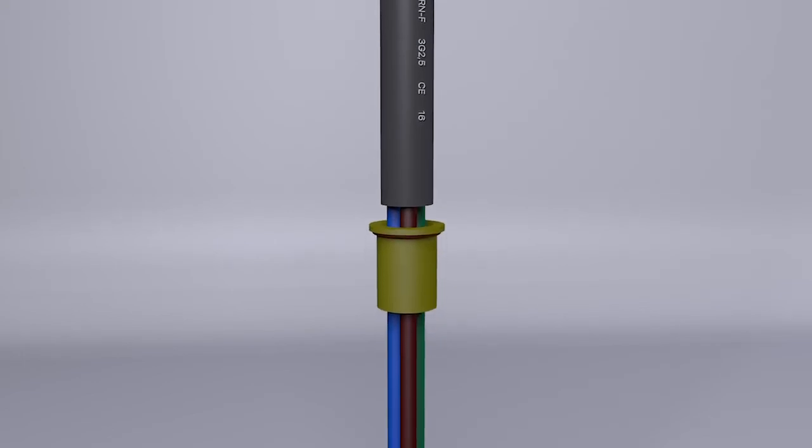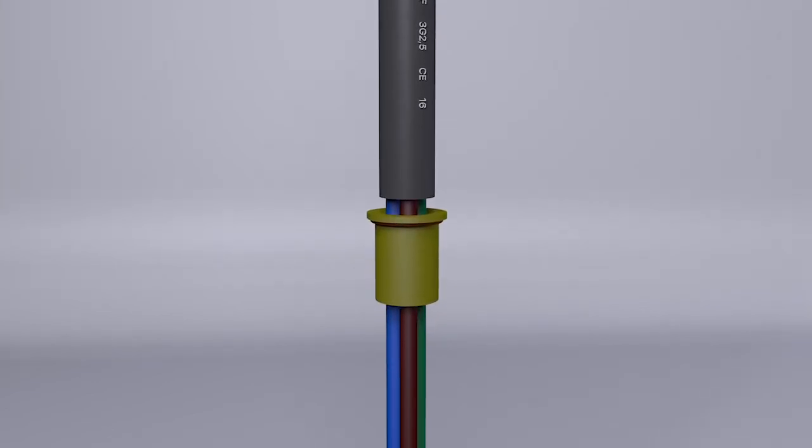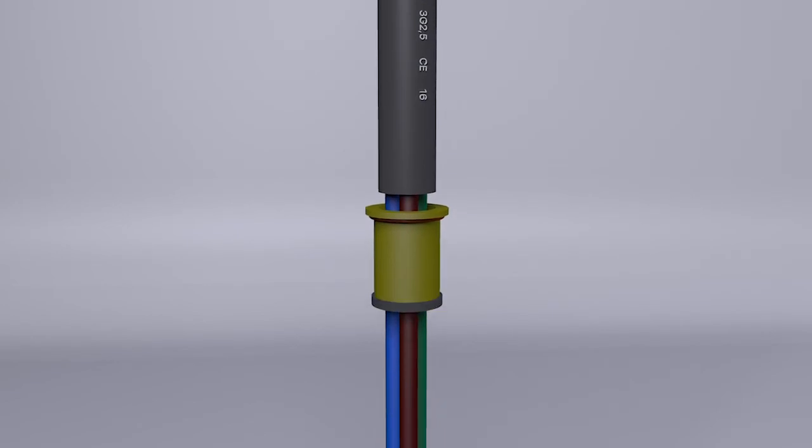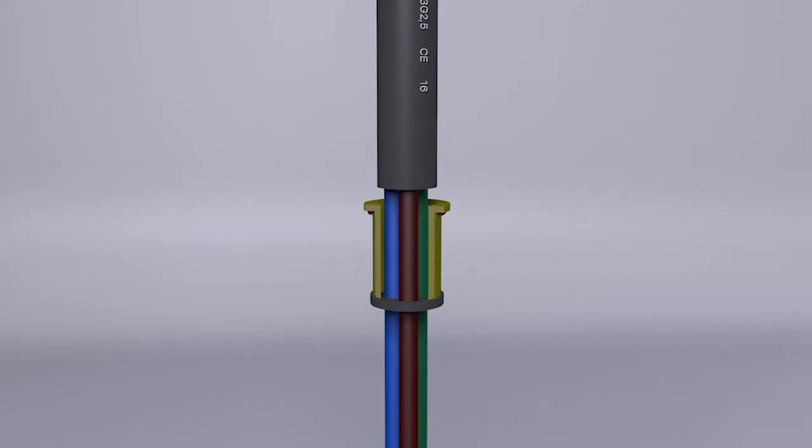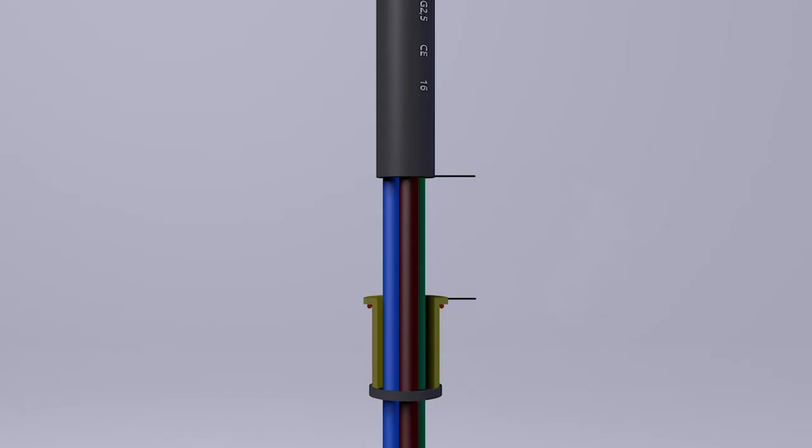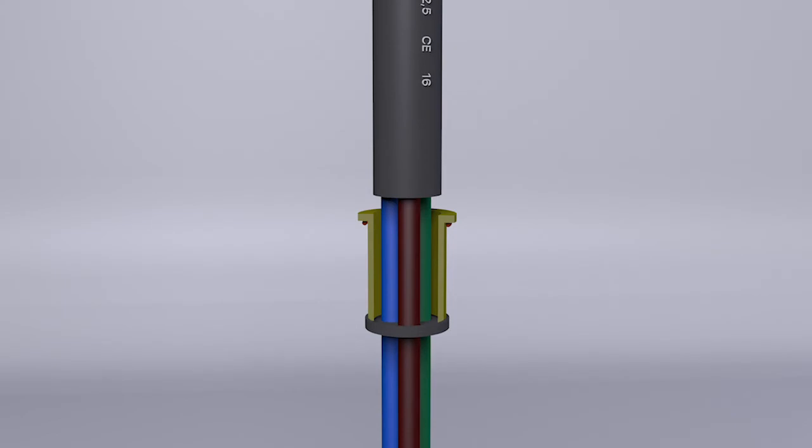Keep the cable in vertical position for the entire duration of the sealing operation. Mount the plug on the sealing bushing. Bring the assembly close to the previously prepared cable, leaving a distance height of 30 millimeters in order to facilitate the introduction of the resin.